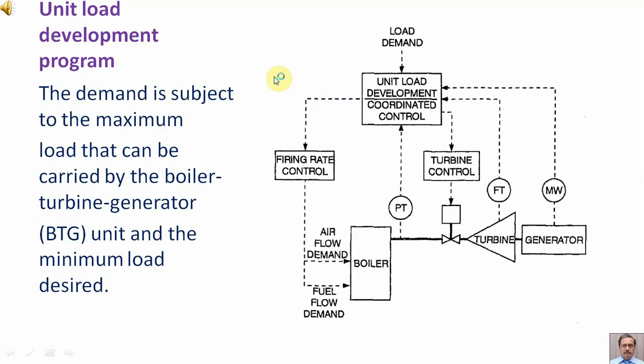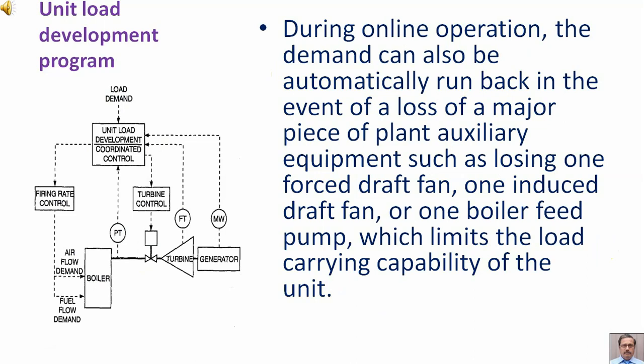The demand is subject to the maximum load that can be carried by the boiler-turbine-generator unit and the minimum load desired. During online operation, the demand can also be automatically run back in the event of a loss of a major piece of plant auxiliary equipment, such as losing one forced draft fan, one induced draft fan, or one boiler feed pump, which limits the load carrying capability of the unit.